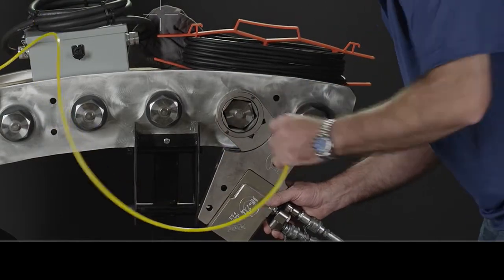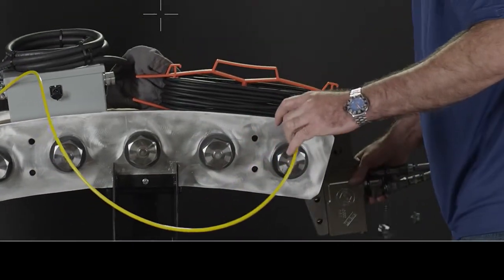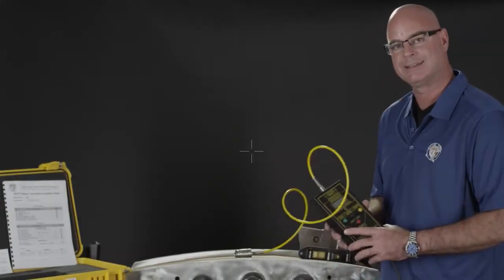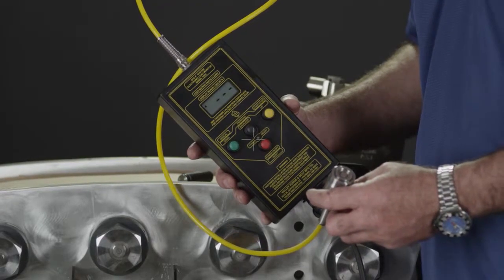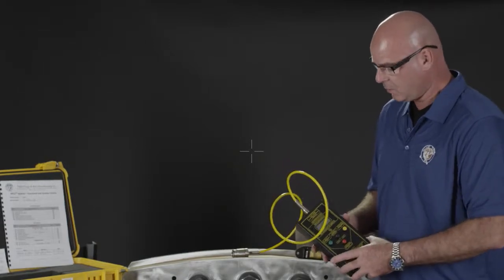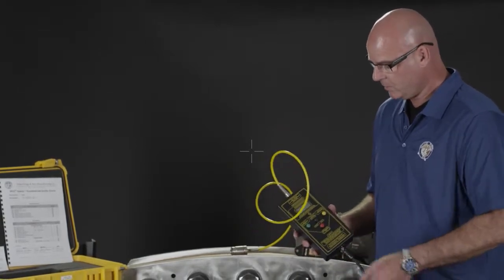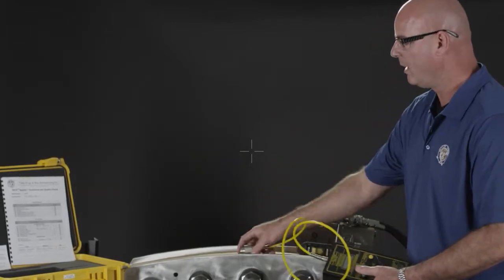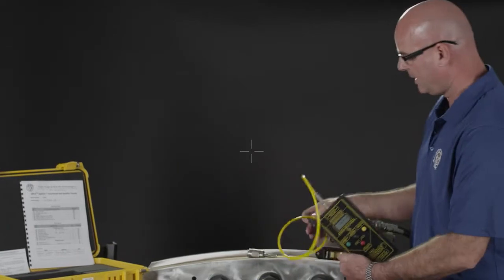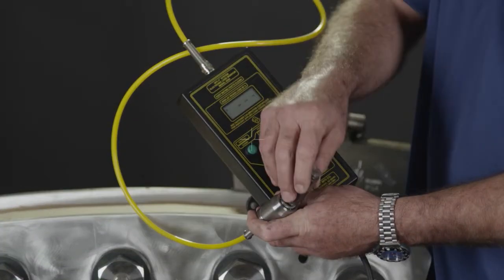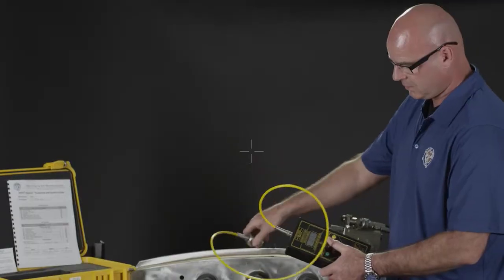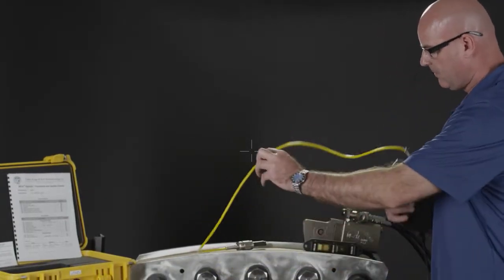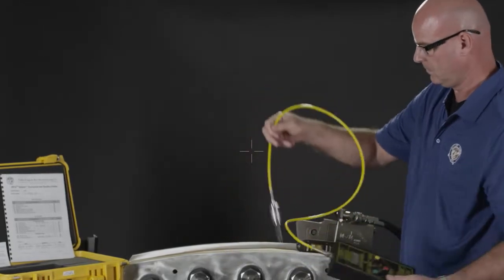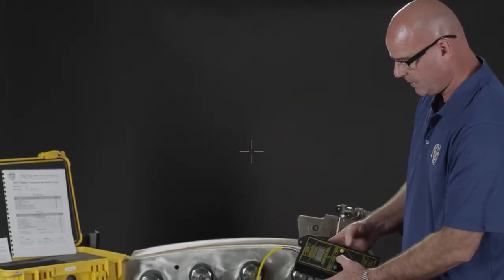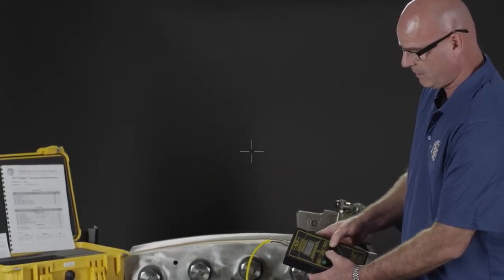So with that, I'll go into the demonstration of the SPC424. We've got a unit that is connected to a hydraulic, pneumatic, or electric torque wrench, or whatever muscle you want to use, as long as it's controllable through a signal. And we control that through an interface cable. We turn the unit on and we program in what bolt load we want to see. So you can do that by attaching your calibration probe to the unit, reading 0, okay, and then when you bring your unit up, you hit the program button and you program it up to whatever you want your stop point to be.